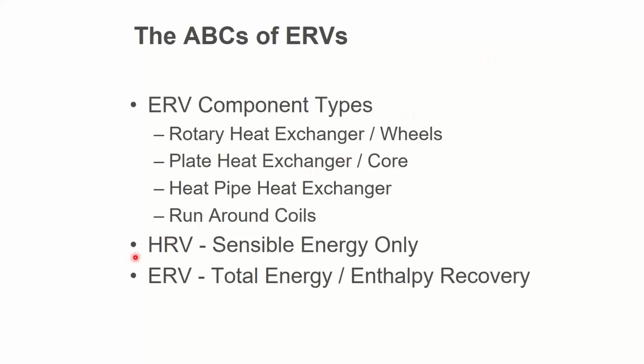There are also terms you might need to know, HRV versus ERV. HRV is heat recovery ventilator. ERV is enthalpy recovery ventilator or energy recovery ventilator, depending on who's saying it. HRVs only do sensible energy, so they only do temperature. They heat up or they cool down the outside air coming in. They do not affect its humidity in any way, no moisture transfer.